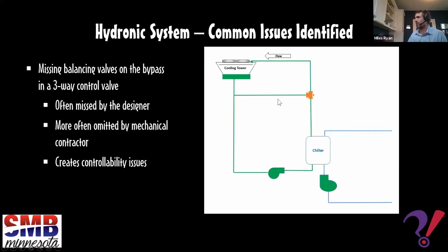And then when it comes to putting a balancing valve there, I think all the ASHRAE guidance, like all the journal articles and the chilled water plant design guide that's out there, are going to say the pressure drop across here should be equal to the pressure associated with a column of water the height of the cooling tower. And that's for controllability reasons, because if you're measuring condenser water supply temperature going into the chiller down here, and you're trying to use this valve to send some of the water to the cooling tower, divert some of it, so your mixed temperature lands on your condenser water supply temperature set point.